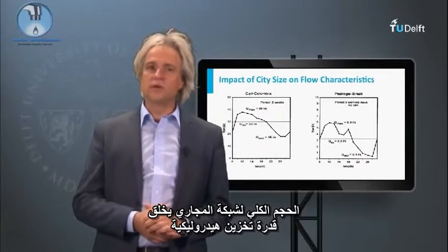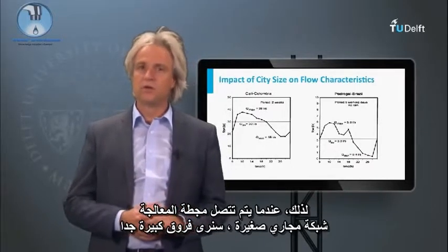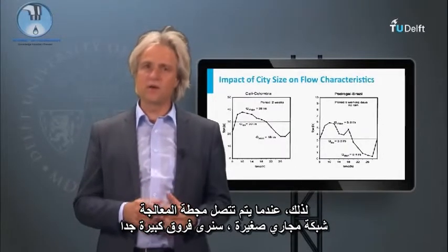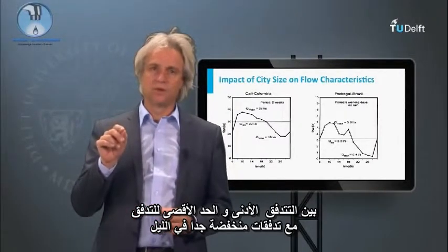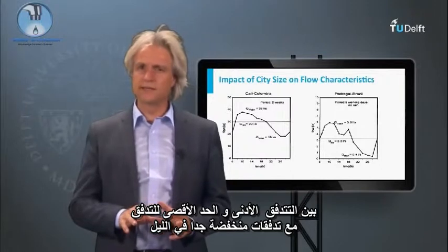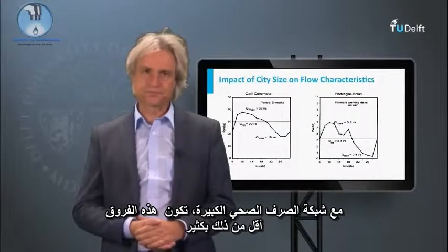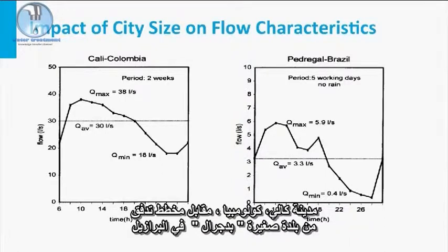The total volume of the sewer network creates a hydraulic buffer. Therefore, when an STP is served by a very small sewer network, we will see a very large flow difference between the minimum flow and the maximum flow, with very low flows in the night. With a large sewer network, these differences are much less. In this slide, you see this exemplified by a sewage flow diagram of the provincial capital town of Cali, Colombia, versus the flow diagram of the small town of Pedregal in Brazil.